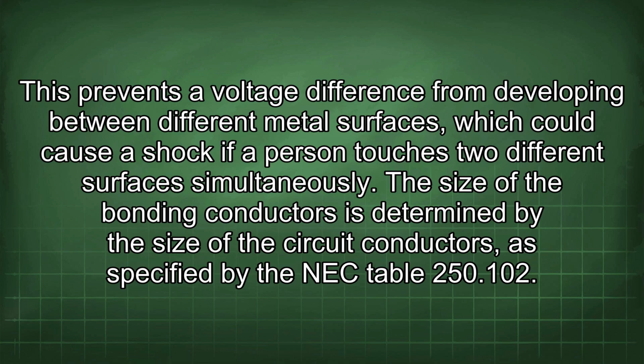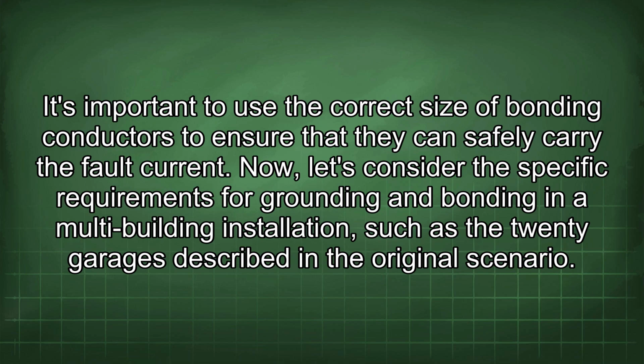The size of the bonding conductors is determined by the size of the circuit conductors, as specified by the NEC Table 250.102. It's important to use the correct size of bonding conductors to ensure that they can safely carry the fault current. Now, let's consider the specific requirements for grounding and bonding in a multi-building installation such as the 20 garages described in the original scenario.